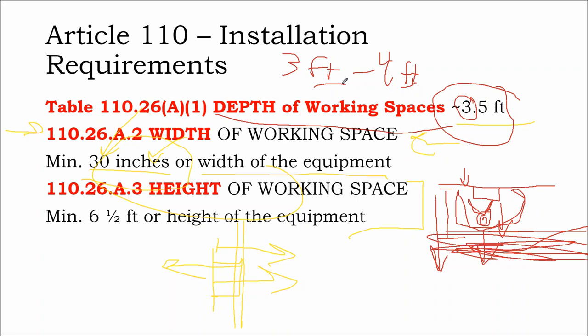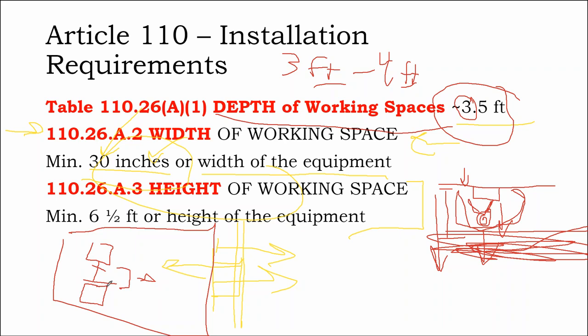Can you imagine a circumstance where you would need something more than 3.5 feet? Let's say there's a wall behind you. The main difference is what's on that wall behind you. Is there just a plain empty wall that you can lean on and back up against and scratch your back on? Or is that wall full of electrical equipment? Are you in a control room and you have an inverter here and you want to know how much space can I have between that inverter and another inverter? Well, National Electric Code says if you have an obstruction behind you and it is electrical equipment, then the space of that dedicated working area needs to be 4 feet. If it's electrical equipment behind you, they don't want you to back into it and electrocute yourself. So they need more space than if there's no electrical equipment behind you.